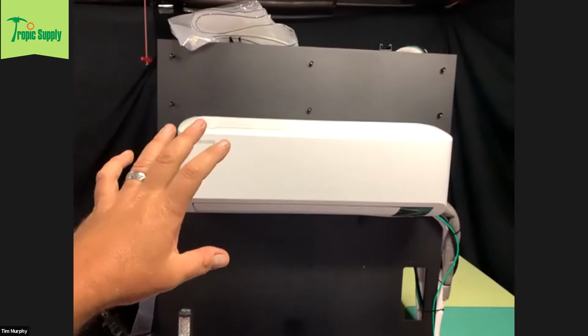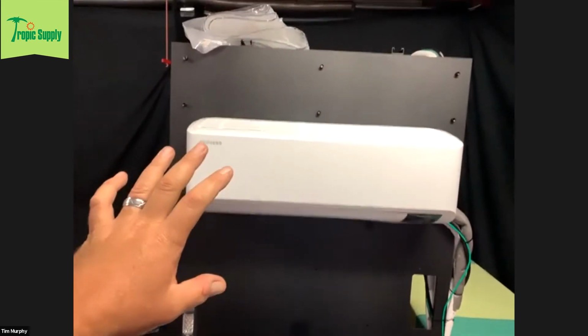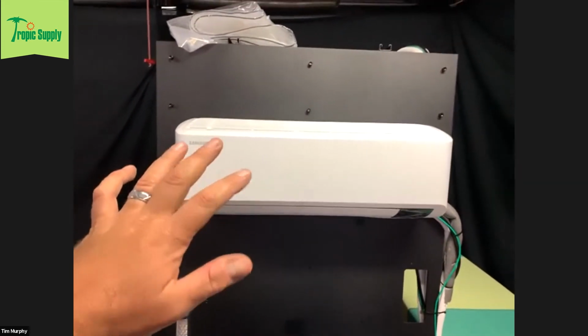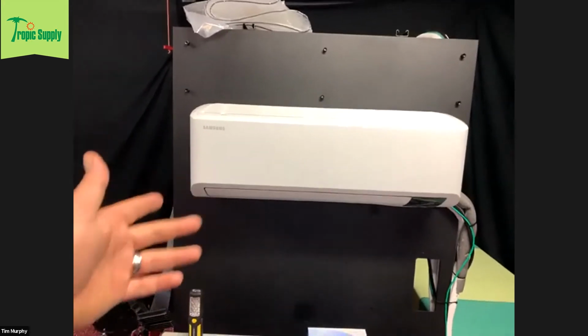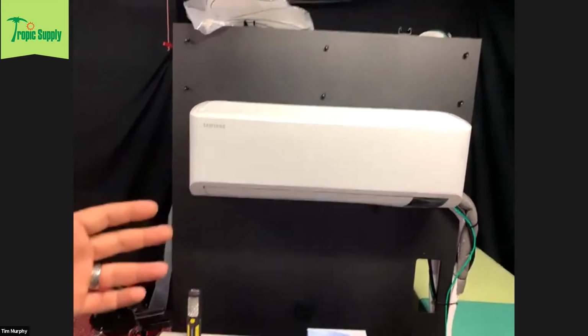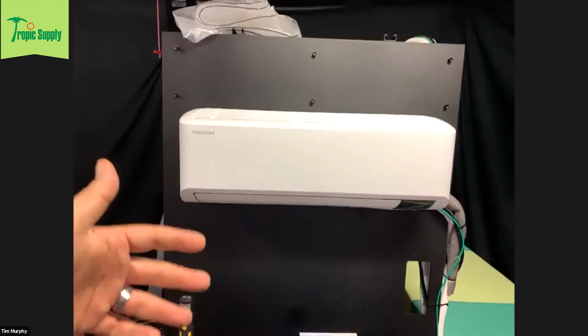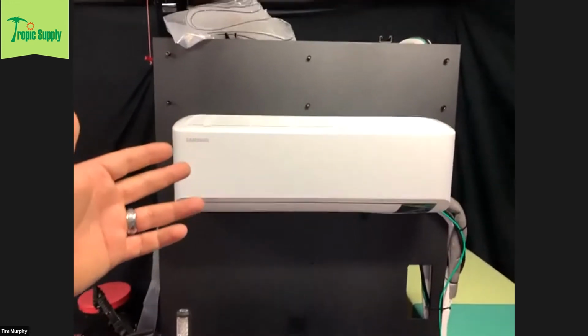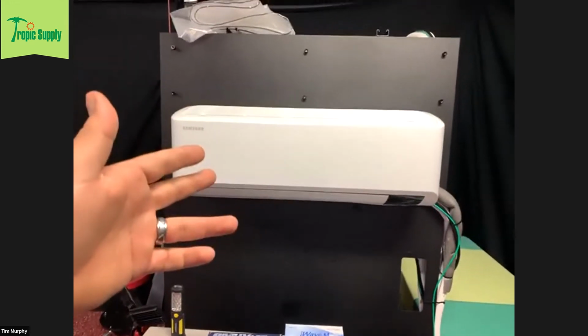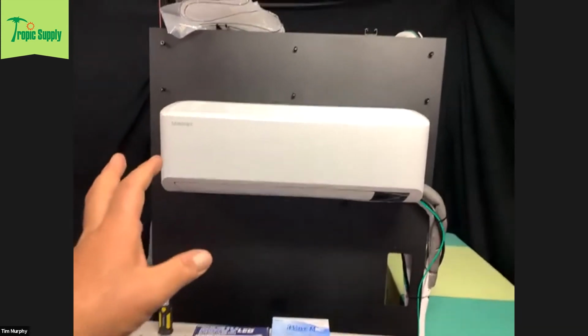With Samsung's mini split systems, they recommend a 3-step leak check process: first at 200 PSI, then at 400 PSI, and if it passes both, you go up to 600 PSI. At 600 PSI, you should get no bubbles or leaks on the flares.